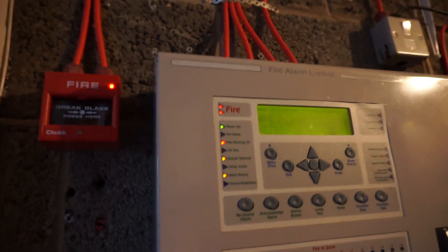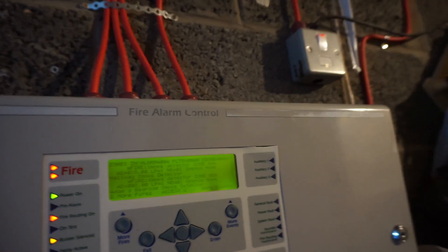So that's everything but the heat detector in the loft - I'm not going in the loft, it's really hard. I'll do signal 2 - sorry, this isn't Gent - function 2, and sound the alert sound and do a little walk around.